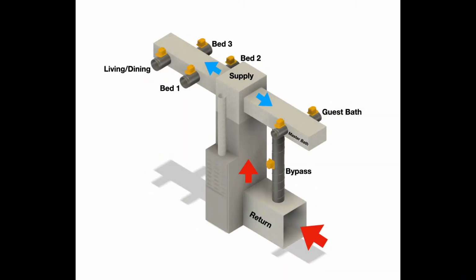Here's a little more complicated model. You can see in this example, the return air comes into the return plenum, goes through the furnace and the evaporator coil into the supply plenum. Then we have air going out to 6 different zone dampers. In this case, bedroom 1 is damper 1, bedroom 2 is damper 2, bedroom 3 is damper 3, living and dining is a 4th one, guest bath is a 5th damper, master bath is a 6th damper. But you'll also notice in this model we have a bypass damper here between the supply plenum and the return plenum. That is there to prevent the buildup of static pressure.